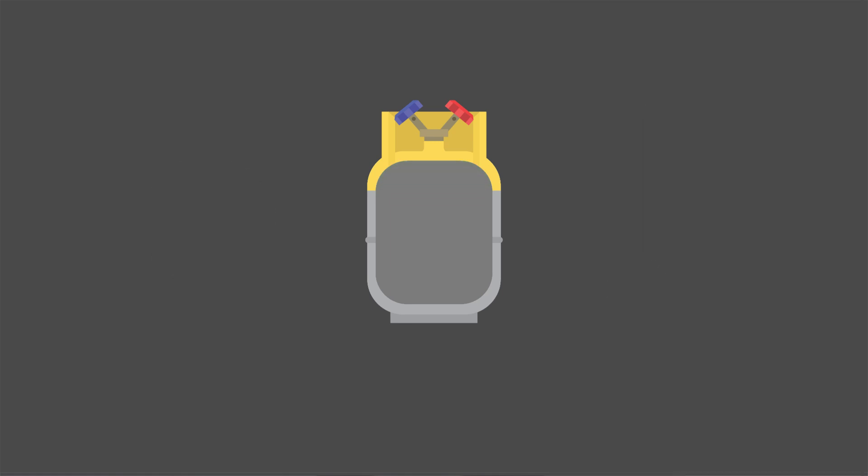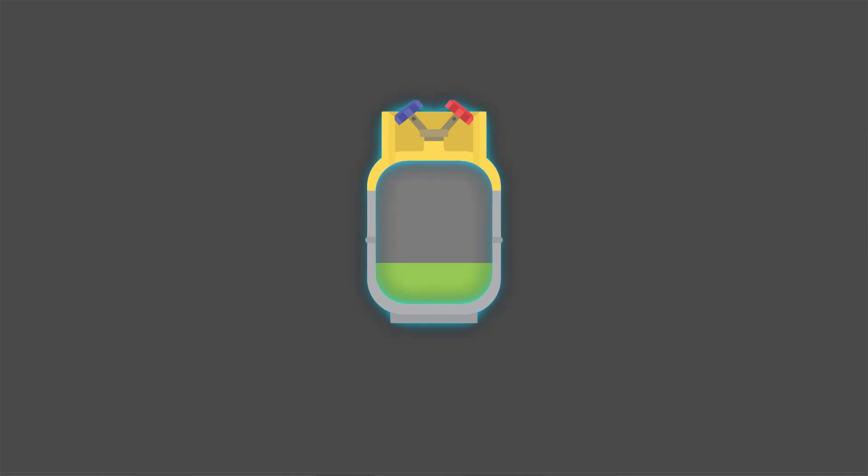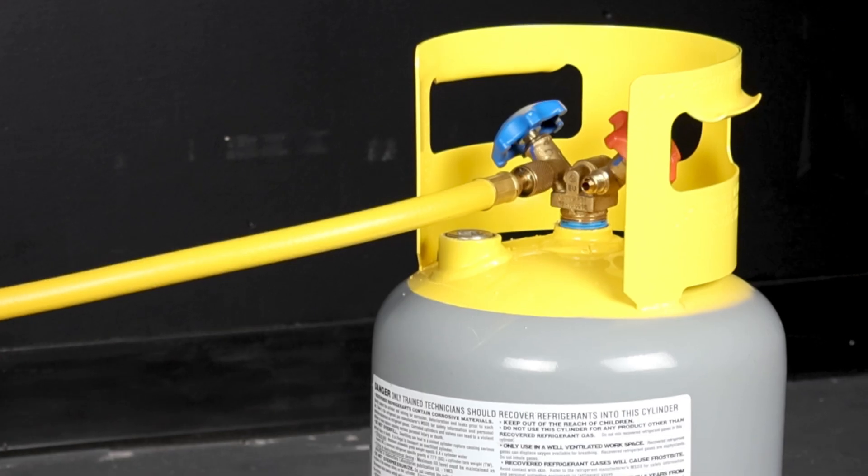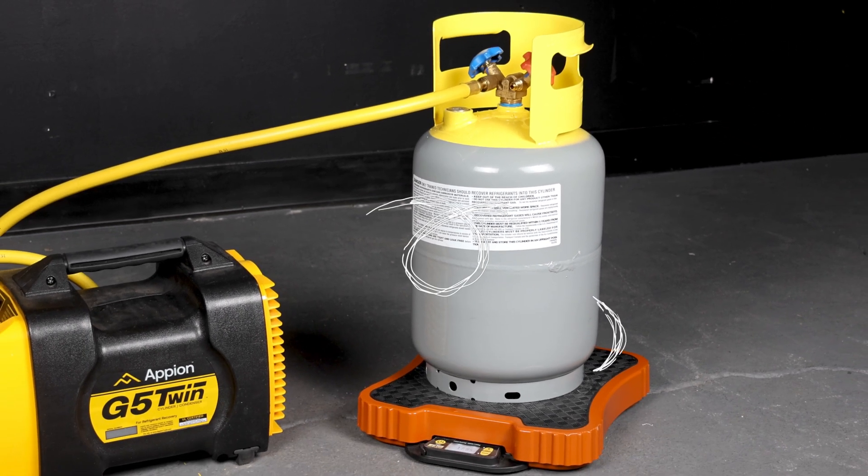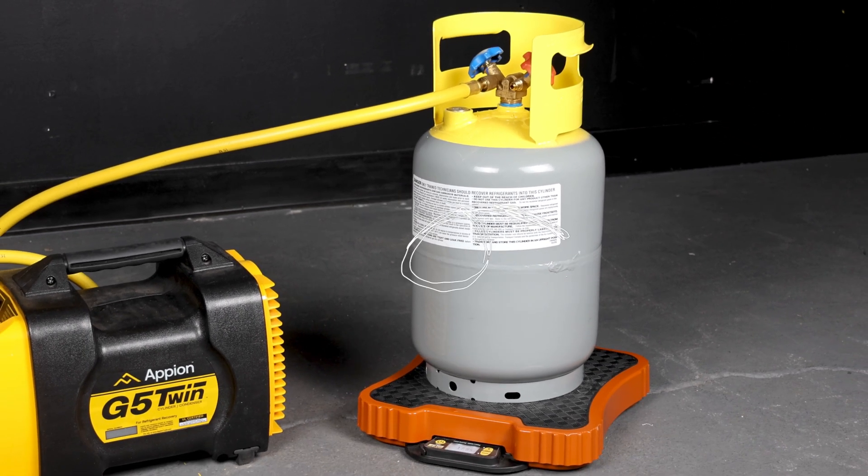The best way to keep the cylinder temperatures low during recovery is to maintain liquid refrigerant flow from the system to the recovery cylinder. In instances where this is not attainable, using the fan from the recovery machine to draw air over the recovery cylinder can help dissipate heat.